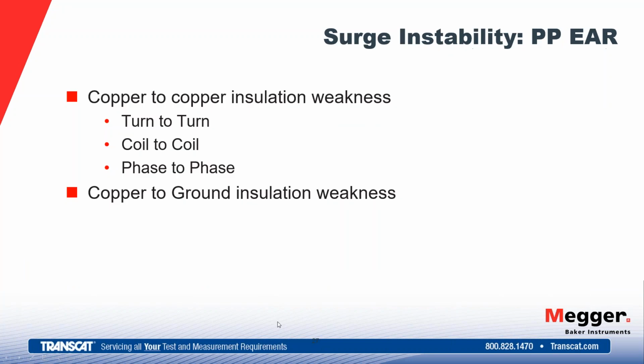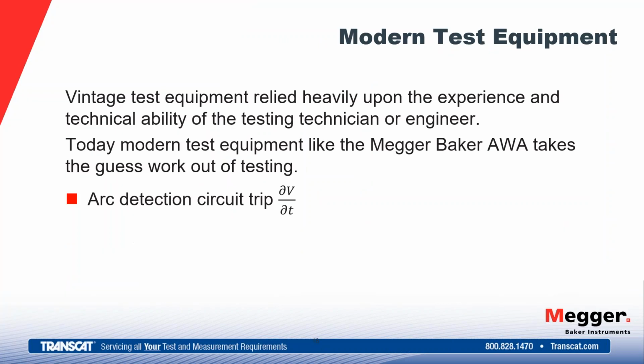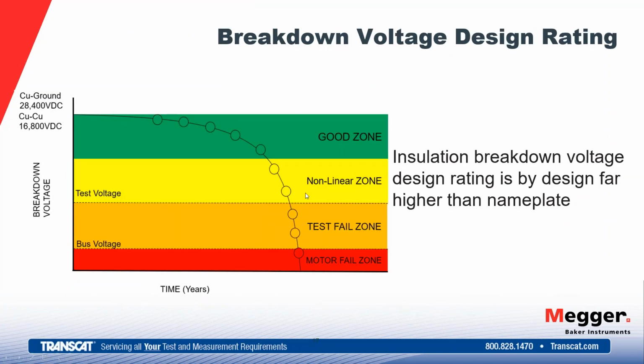So the graph here, if I find it again, oh, that was it. Here, again, is the insulation life curve. This point here that's in red, that's the motor fail zone. If our dielectric strength or breakdown voltage falls below bus voltage, we have catastrophic failure. The orange area represents the voltages at which switching current surges occur, and this is what our tests are designed to catch. So when we fail a hipot test or the surge test, we would place the motor here, depending on which voltage it failed at. This would be the test fail zone.